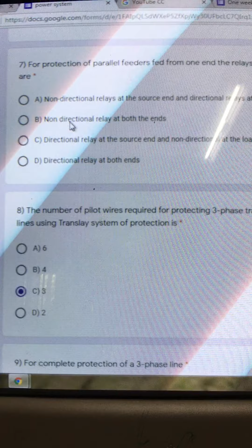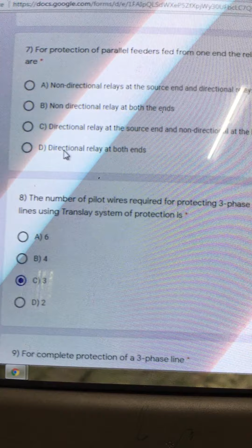What is a non-directional relay? A relay which operates irrespective of the flow of current is said to be a non-directional relay. What is a directional relay? A relay which trips on source current, preventing current from flowing back into the source, that is, it is directional. Remember, directional relay is always placed at the incoming side, non-directional relay is always placed at the source side, and directional relay at the load end. So the correct option for question number 7 is non-directional relay at source end and directional relay at load end.